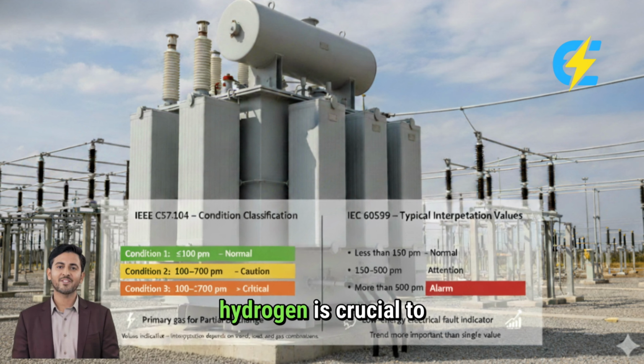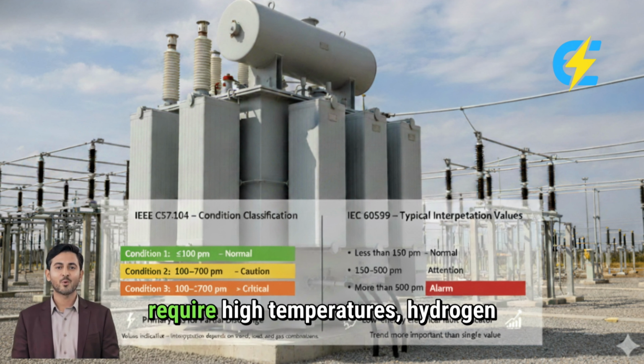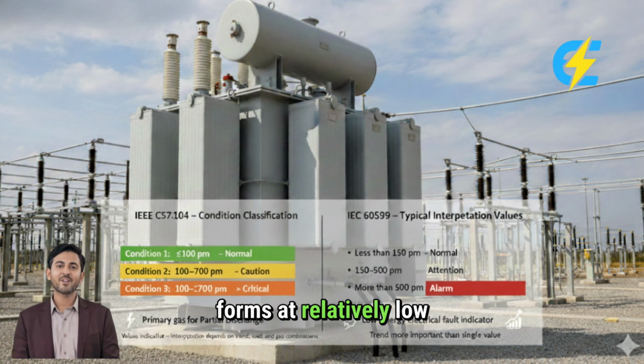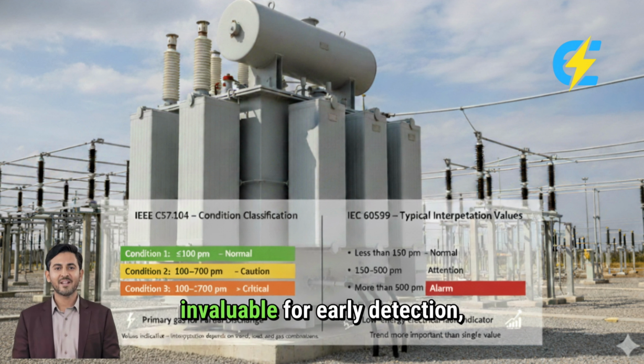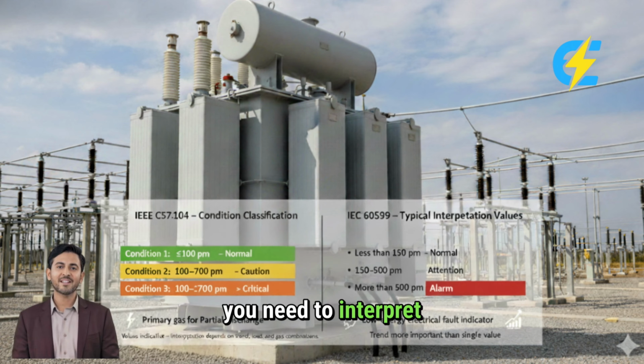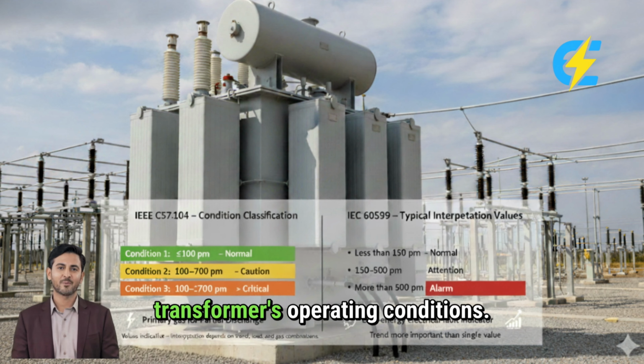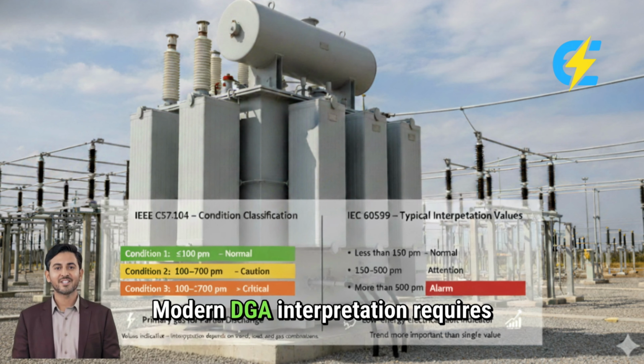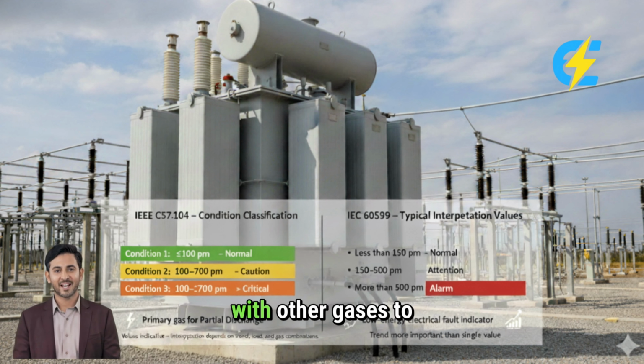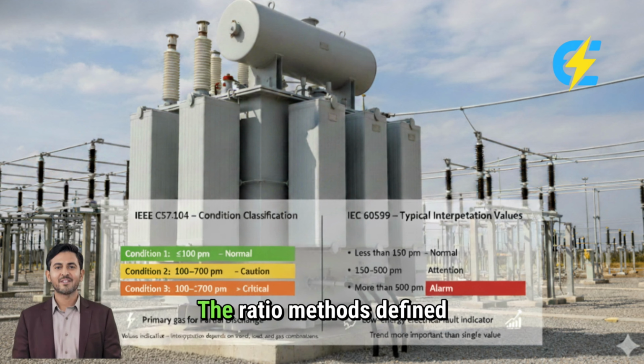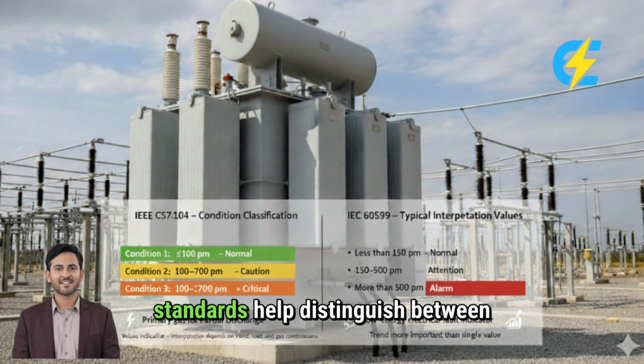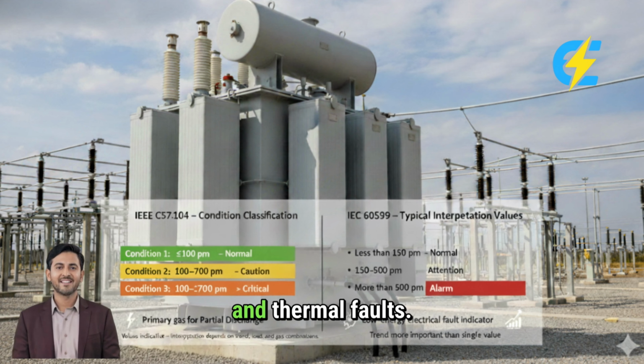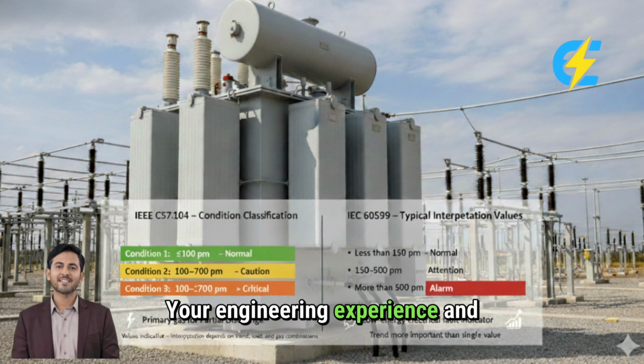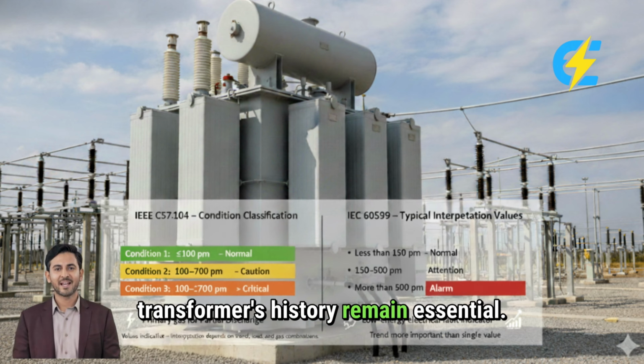The formation mechanism of hydrogen is crucial to understand. Unlike thermal gases that require high temperatures, hydrogen forms at relatively low energy levels. Even minor electrical stress can begin hydrogen production. This sensitivity makes it invaluable for early detection, but it also means you need to interpret results carefully within the context of your specific transformer's operating conditions. Modern DGA interpretation requires analyzing hydrogen in conjunction with other gases to identify fault patterns. The ratio methods defined in IEC and IEEE standards help distinguish between different types of electrical and thermal faults. But remember, these are guidelines, not absolute rules. Your engineering experience and understanding of the specific transformer's history remain essential.